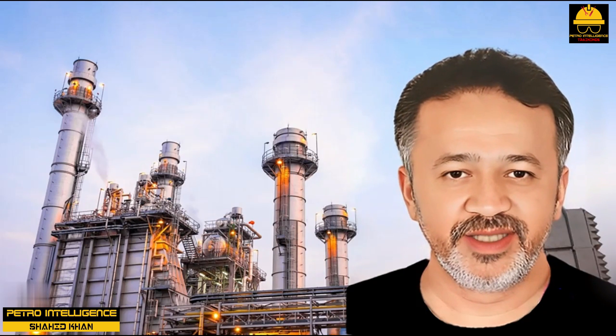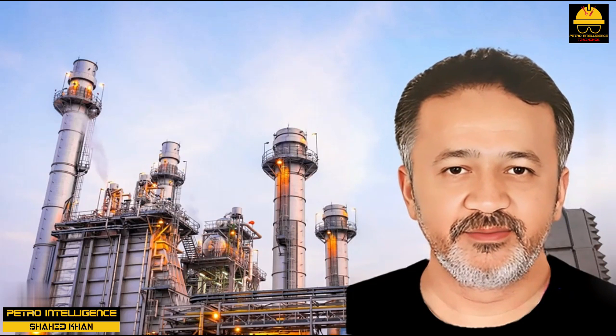The temperature of the tubes may approach the temperature of the refractory at the point in time when flow is lost. The refractory temperature is indicated by the firebox temperature or the temperature of the flue gas flowing from the firebox into the convective section. A typical firebox temperature is 1500 degrees Fahrenheit. Thus, the heater tubes can reach 1300 degrees Fahrenheit on loss of the process flow, even though the fuel flow has been immediately stopped.